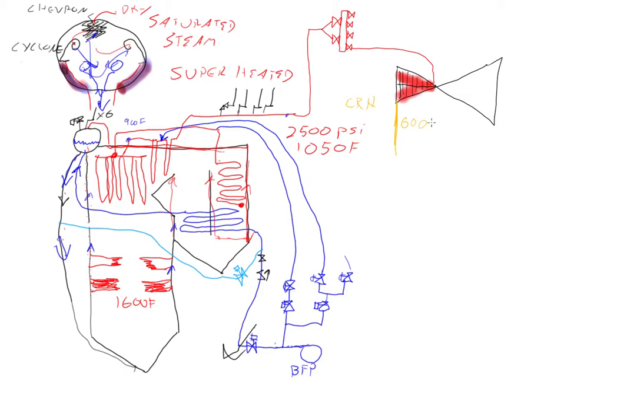Cold reheat steam is somewhere around 600 psi and 600 Fahrenheit. Now this 600 Fahrenheit is lower than saturation temperature at 2,500 pounds. 2,500 pounds saturation was around 670 Fahrenheit, so we have given up a lot of heat throughout this process. As we give up heat we come closer to saturation.